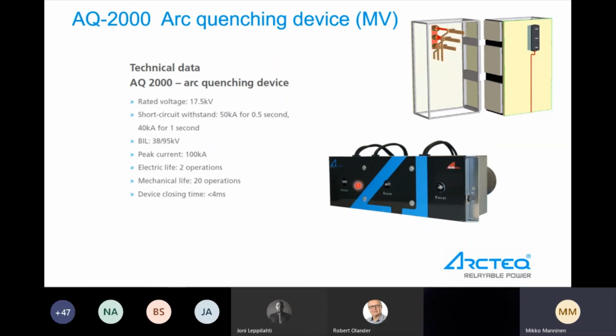So when we do the recharging for this unit, this has to be pulled out. And very easily one of the micro switches is not connected, and then the loop is open. There are 3 micro switches here, and when the loop is open, it doesn't start.